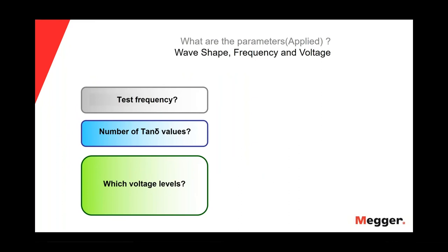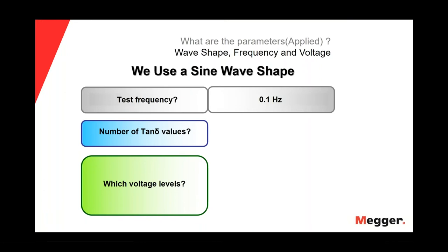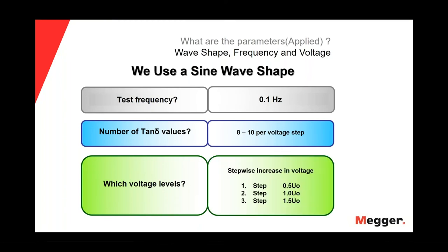So, what are the parameters we will apply? Well, first of all, we will use a sine wave shape. The test frequency must be 0.1 Hz. We will measure between 8 to 10 values of tan delta per voltage step, and we will apply three voltage steps. The first one will be 0.5 U0, the second one 1.0 U0, and the last one 1.5 U0.